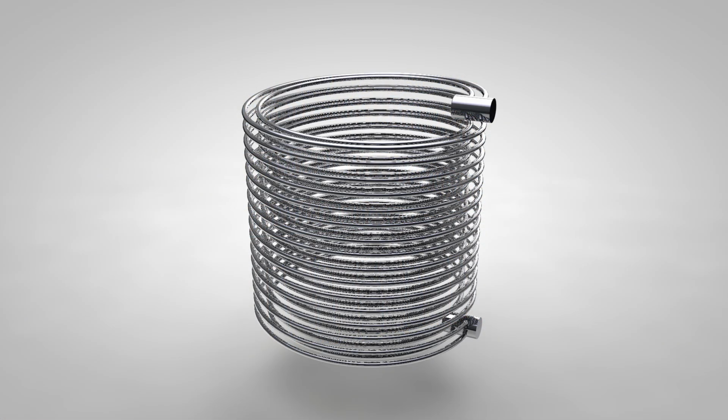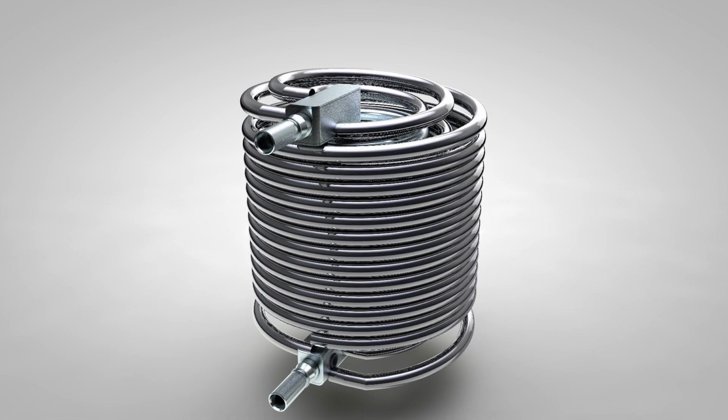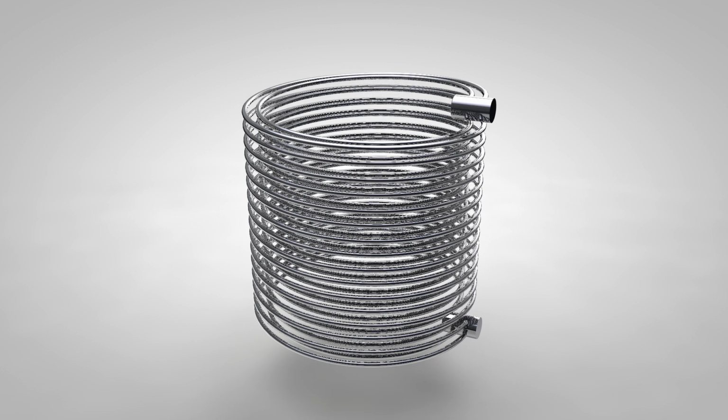4. The final common way of increasing coil surface area is to use a manifold design, with multiple pipes linking into two manifolds at each end with Boss connections. These can be just a few pipes or lots of very small ones, allowing you to achieve a very large surface area inside a very small amount of space. The small bore version restricts flow rates, resulting in a high-pressure drop across the coil. The manifold design can also shorten the working life of the cylinder.